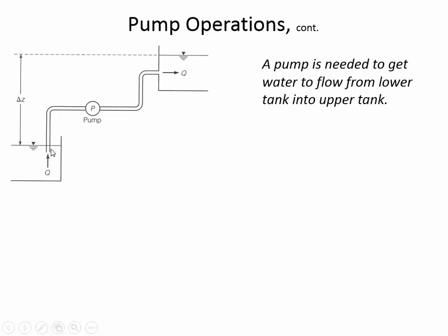And so here in the system we've got an entrance loss where energy is being lost just because of turbulence here. Here's going to be a local loss, another one there, here at this bend, and then a discharge loss. So those are the local losses, but then there's also frictional losses that the pump has to overcome, and then finally a delta Z. And so we can represent the amount of energy that's required to overcome this system as a function of the flow rate. And that's just what I've drawn here, a typical shape of what we're going to call the system curve.